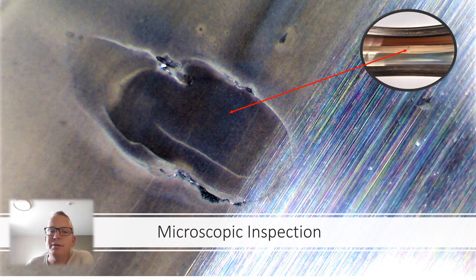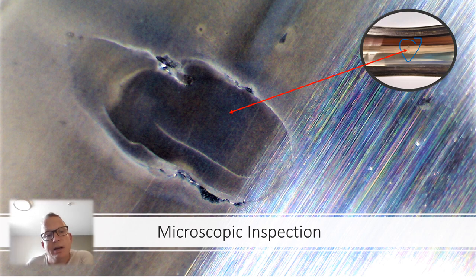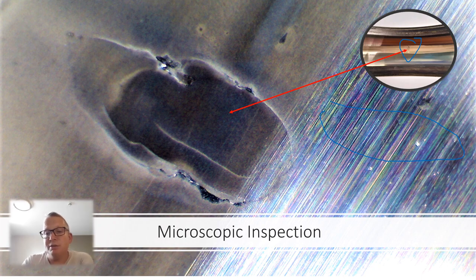And under a microscope here, and here we can see cracks, subsurface cracks and starting to lift. And you can even see here, all this bit here, that's the grinding marks when they made the bearing, which is this bit here. And we've got the dull path here with a couple of discharges from the rolling track. So this actually detected this. So that would have been in the deep load zone, subsurface fatigue and crack.